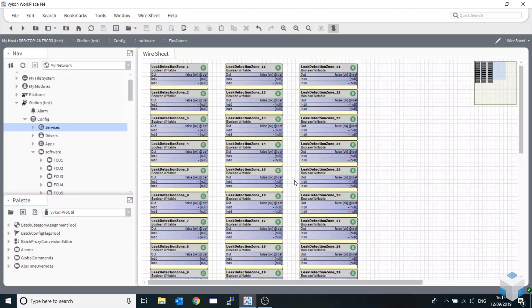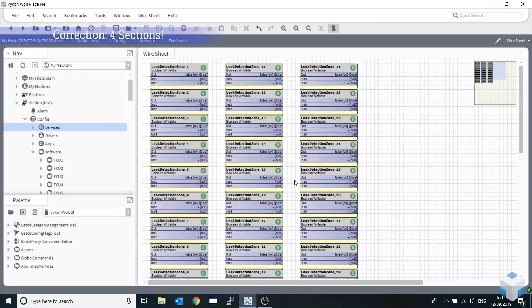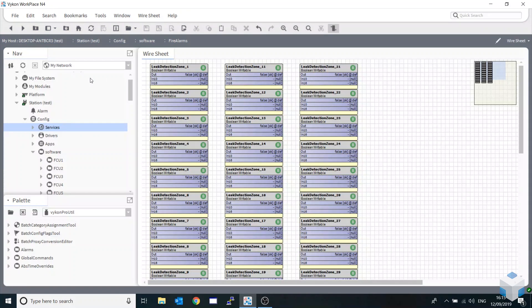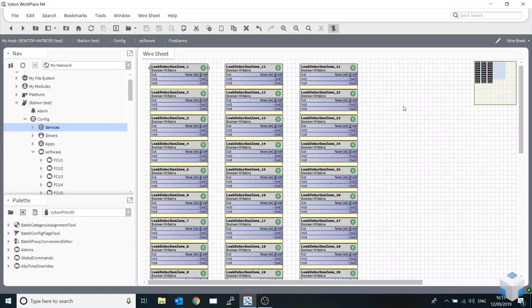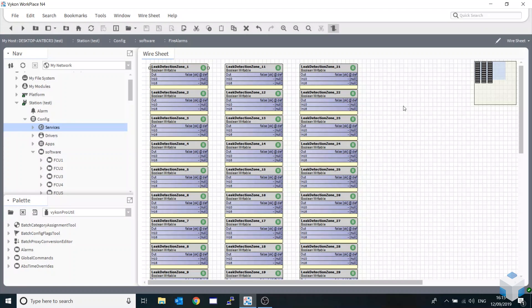We'll do this in a breakdown over three sections of this video. Let me show you one thing straight away. We've got the alarm detection zones - these are just boolean writeables, pseudo points for examples. I'm going to show you how using a naming convention you can actually mass change these in one hit. This will be very handy for things like commissioning if you need to see if your heating valves are working correctly over a floor.